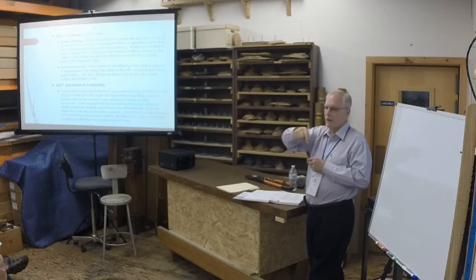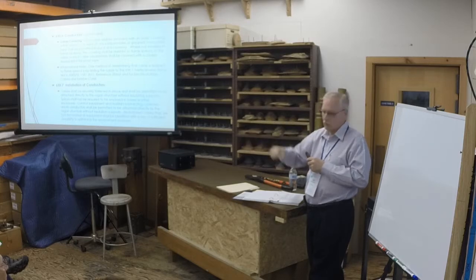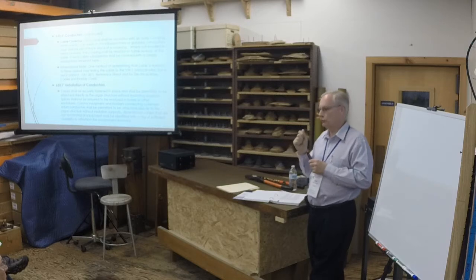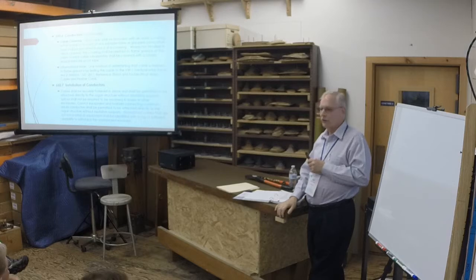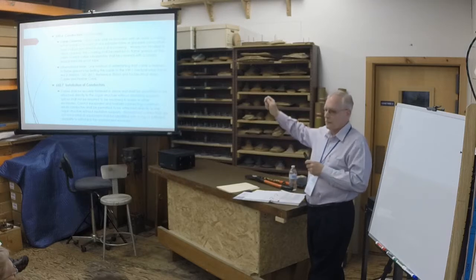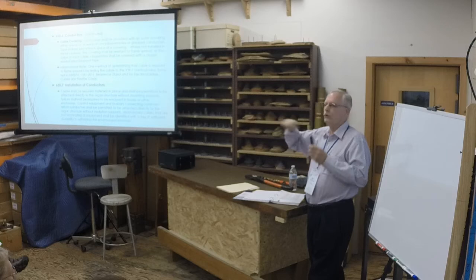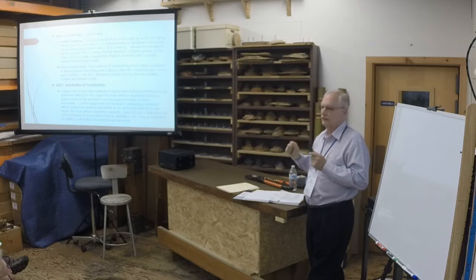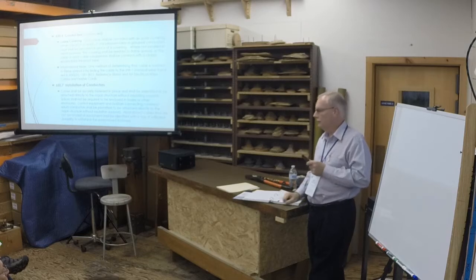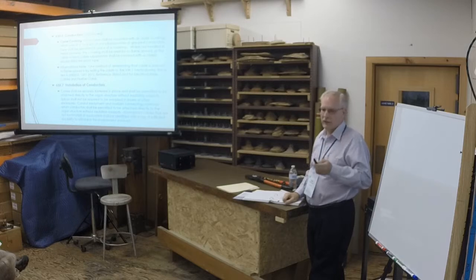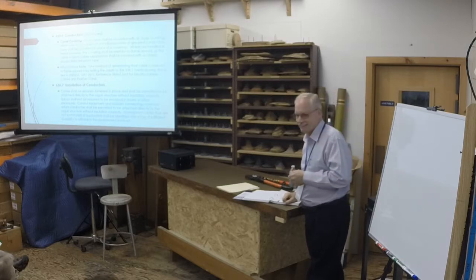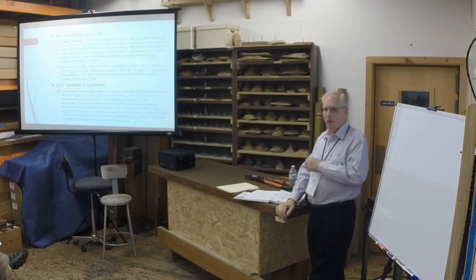And oh, by the way, in the manila folder was a sample of a cable tag, and also the sheet that you can make those from. So you can use it for your regular cabling, and in this case all you do is write 'abandoned' on the tag, and that makes you legal and safe. Both ends of the cable have to be tagged.